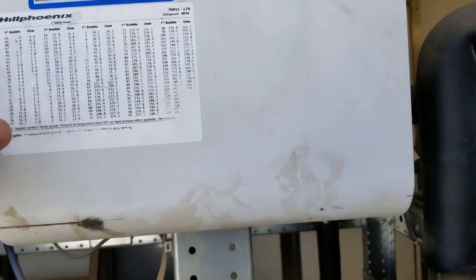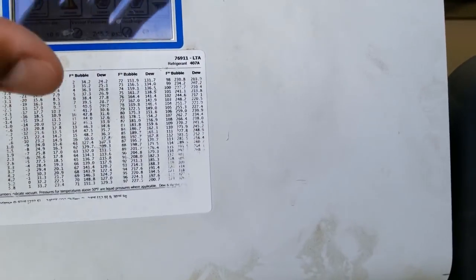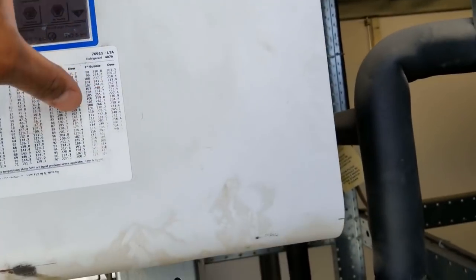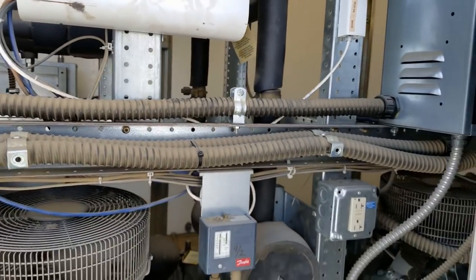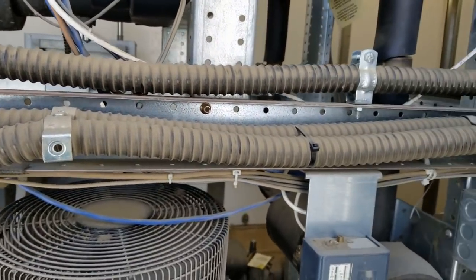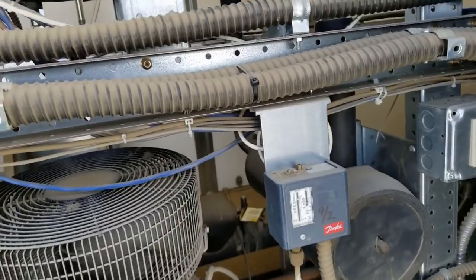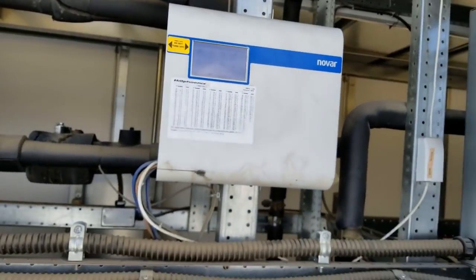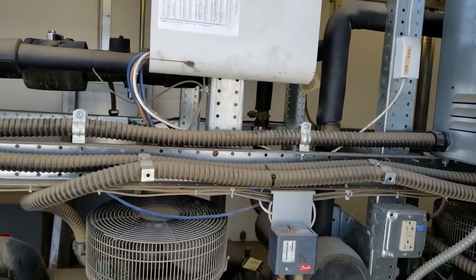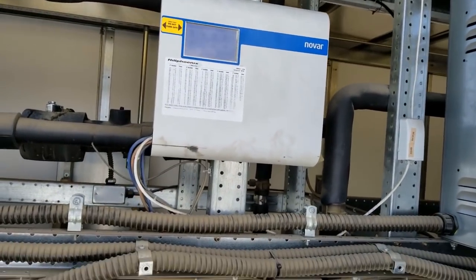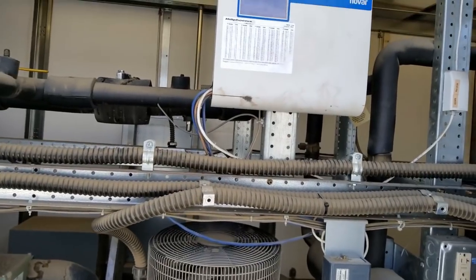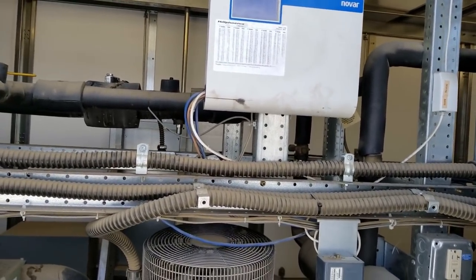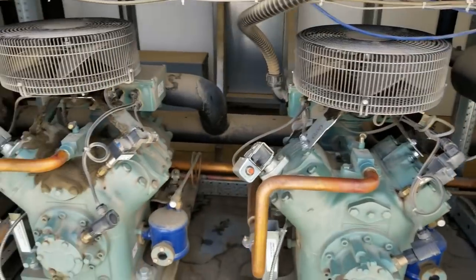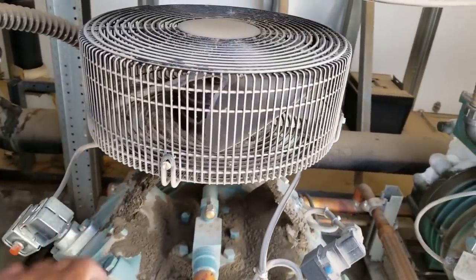Okay, I can't really see too good. I'm not going to really show you the screen that much. It's too sunny right now. It's hard to see. But this controller controls just the rack and the condenser and basically everything on this rack. CO2, compressors, condensers. Everything else, the cases and so on, there's another separate controller just like this one in the electrical room that controls just the cases, defrost, and so on and so forth. So right now we're gonna get into this one here, but real quick, I'm gonna give you a quick overview of this rack.